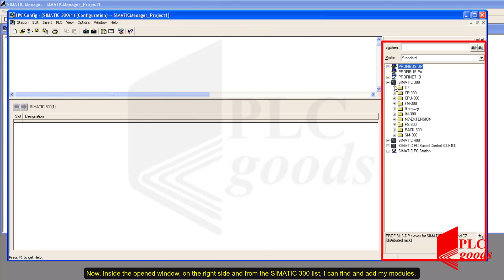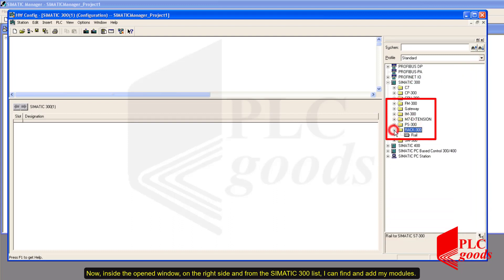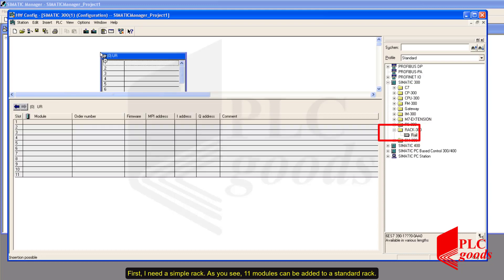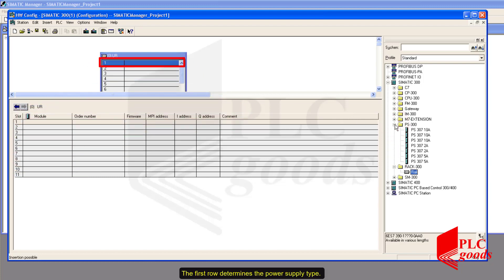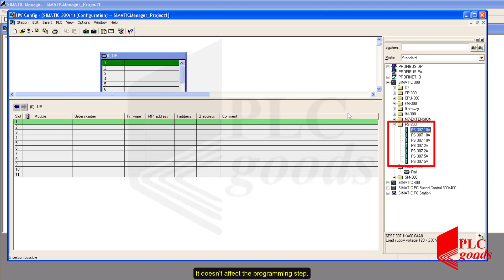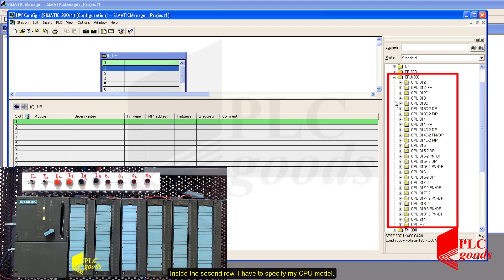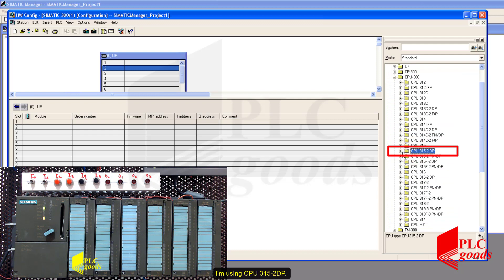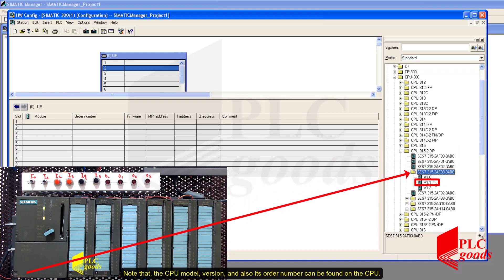Inside the open window, on the right side, from the Simatic 300 list I can find and add my modules. First I need a simple rack. As you see, 11 modules can be added to a standard rack. The first row determines the power supply type. Because I'm not using any Siemens power supplies, let me leave the first row — it doesn't affect the programming step. Inside the second row I have to specify my CPU model. I'm using CPU 315-2DP. Note that the CPU model version and order number can be found on the CPU.